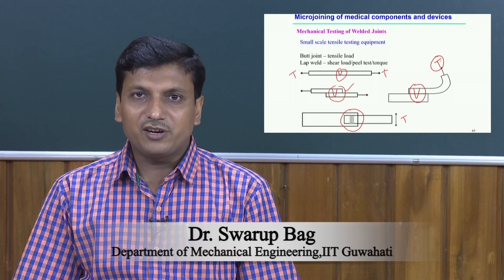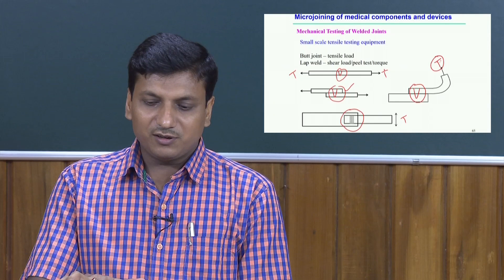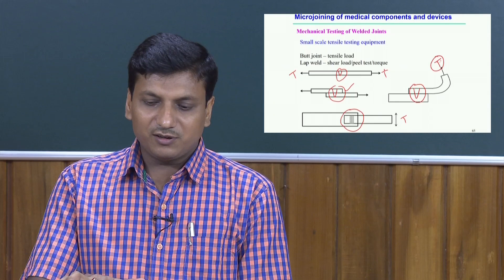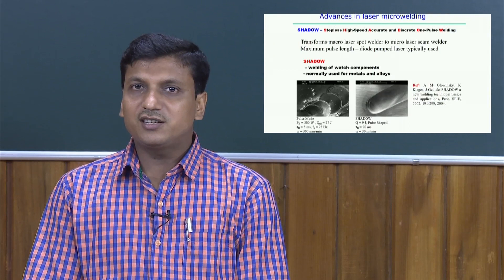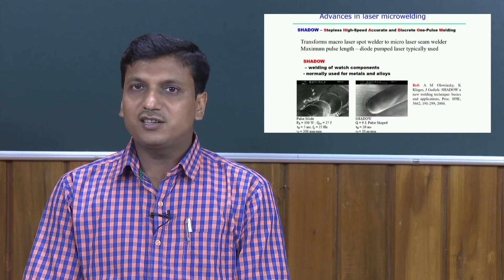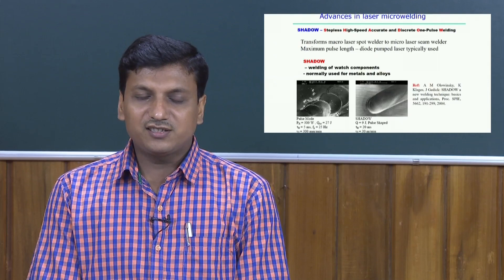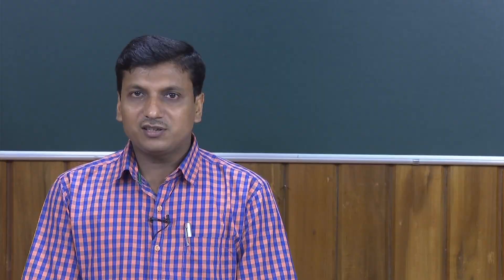After analysis of medical electrical components, we look at advancements in laser micro welding processes. Several advancements have happened in micro welding technologies specifically using laser. One such technique is the SHADOW technique, which stands for Stepless High-speed Accurate and Discrete One-pulse Welding. The principle transforms a macro laser spot weld into a micro laser seam weld.